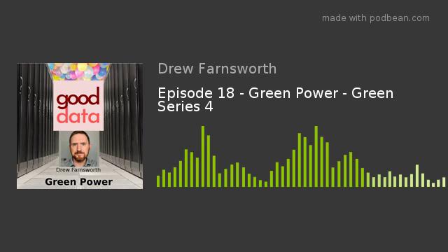So the eco mode is something that I personally don't recommend. I think it's a real problem, and something that's been problematic for a lot of installations. There are other types of UPSs, though, and we can talk about those briefly.